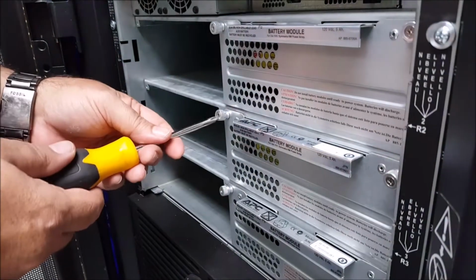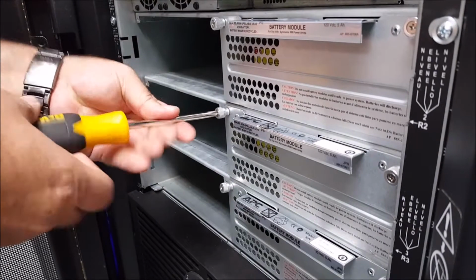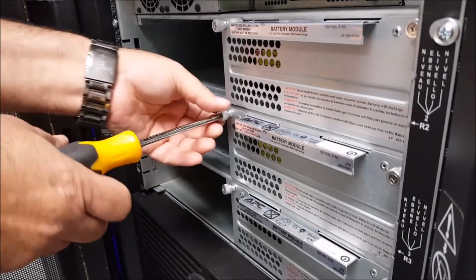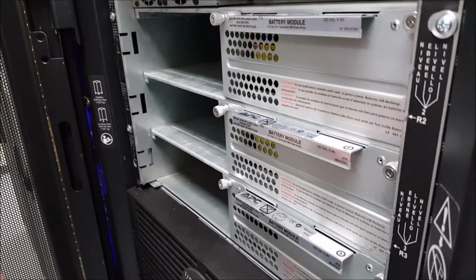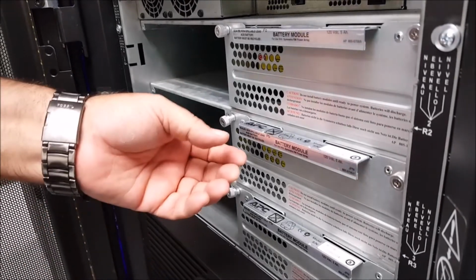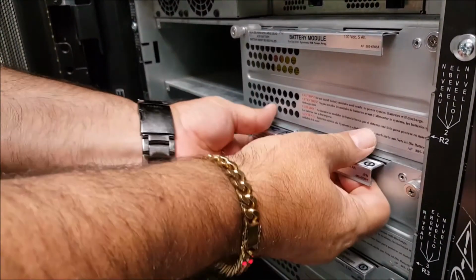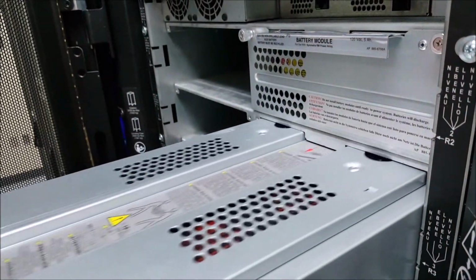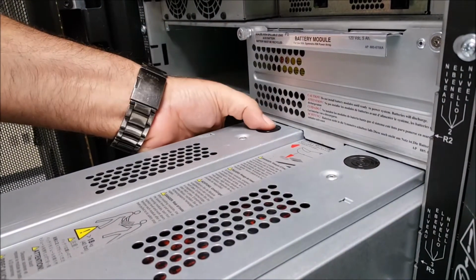Please note that if you have any extended run frames, adding additional battery capacity to your Symmetra RM unit, in order to make sure that no DC power is being supplied to the unit, you'll need to either disable the battery modules in the same way for those as well, or you'll need to disconnect the cable that goes from the back of the extended run frame to the back of the Symmetra RM unit.